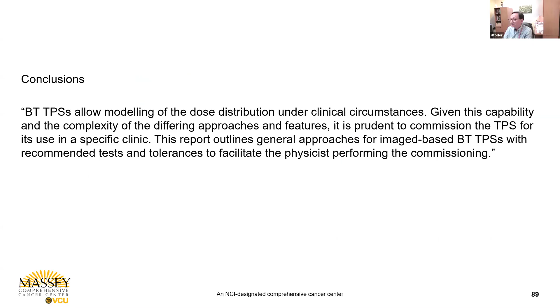And you can see here, that's the conclusion of the document that I was just sharing with you: the brachytherapy treatment planning system allows the modeling of dose distribution under clinical circumstances. Given the capability and the complexity, they say it's prudent, so they don't say it's mandatory, but prudent, to commission the treatment planning system for its use in a specific clinic with specific applicators.